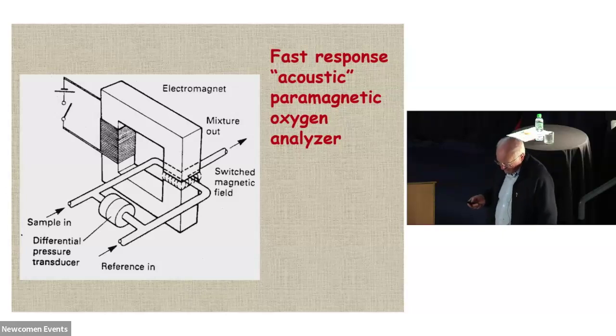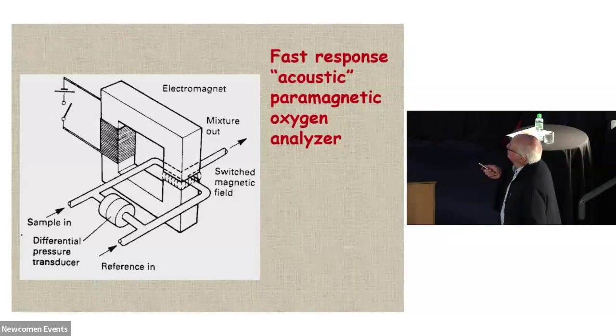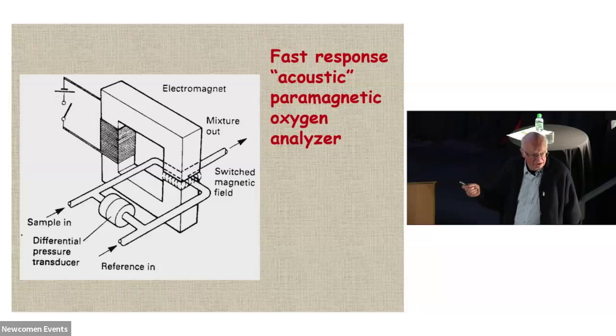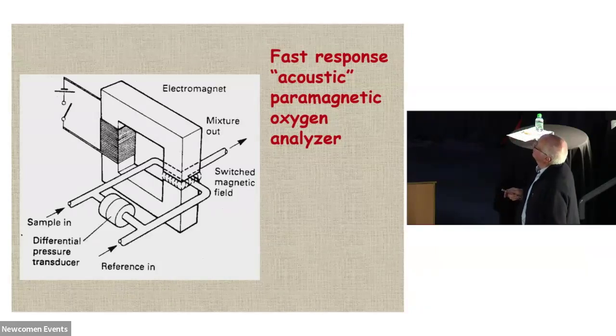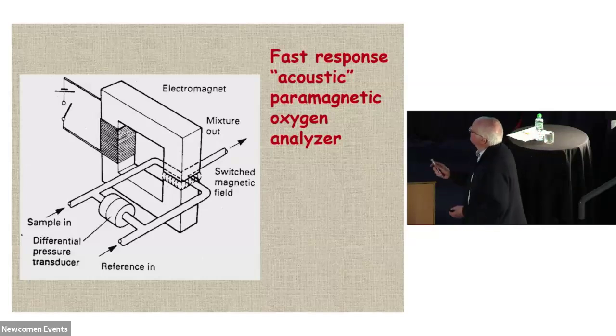The way that you could use this paramagnetism in anaesthetic machines or on monitoring systems in the intensive care unit, using this paramagnetic effect, you had two gases. One here was the reference, which was usually just air, and you hoped it was the normal 21% oxygen. And the sample, a very small sample, was being drawn through here by a pump in the machine from the circuit near the pipe that was delivering gases to the patient. And there was an intermittent magnetic field, very rapid here, and this was like a little microphone, a differential pressure transducer here. It was amplified and calibrated, and so you got a very accurate level of the amount of oxygen that you were drawing into it.